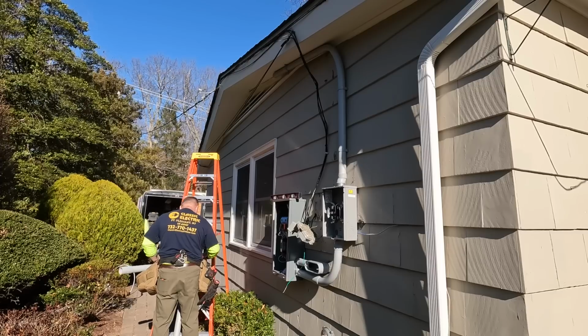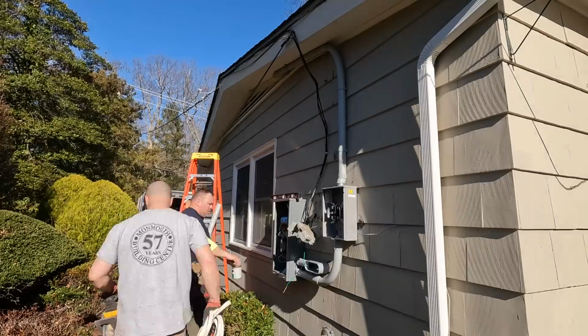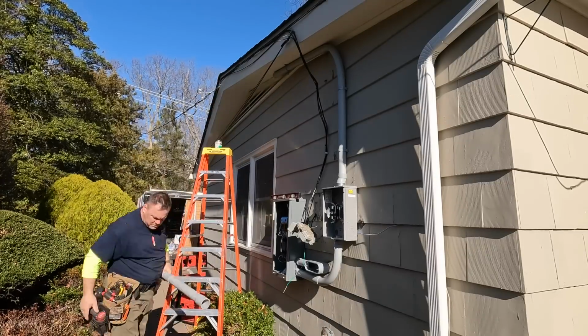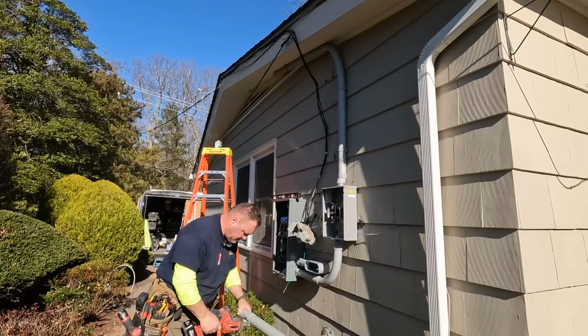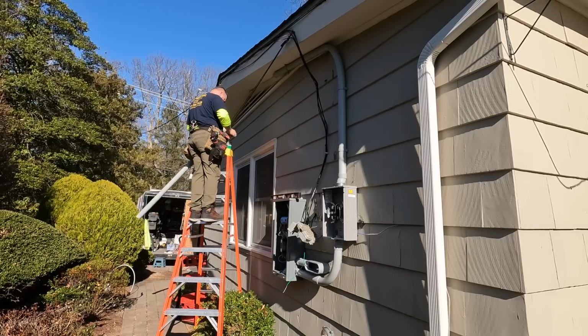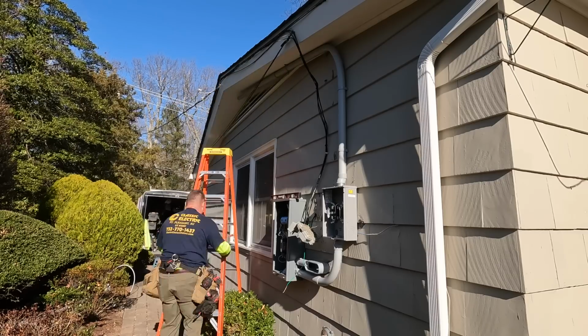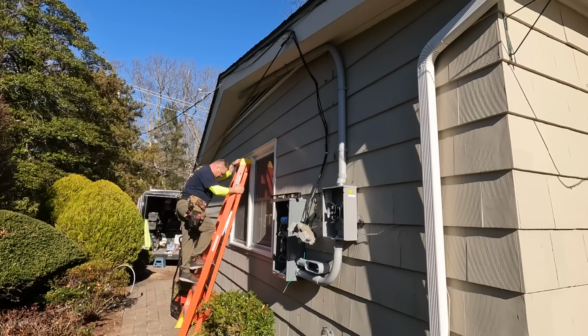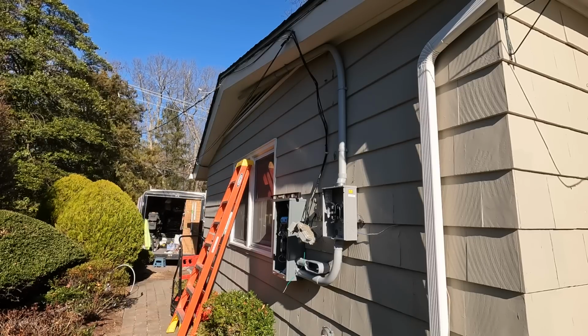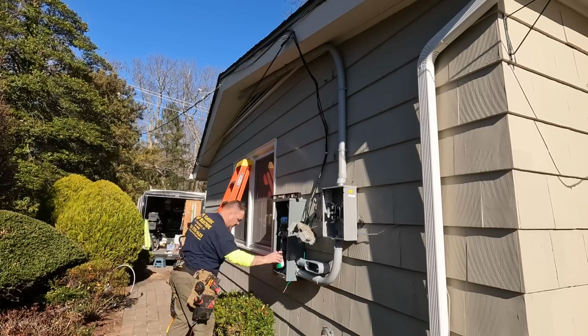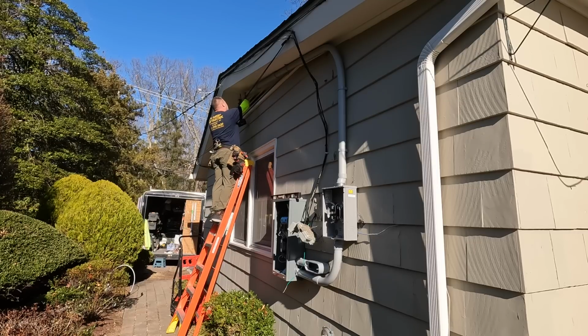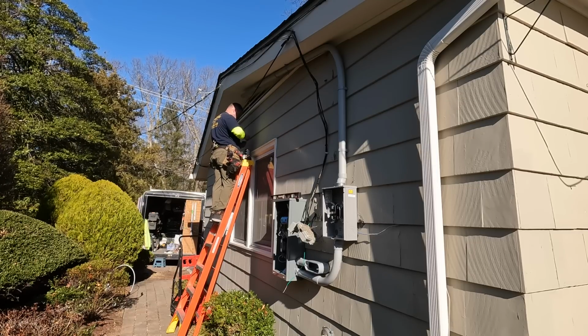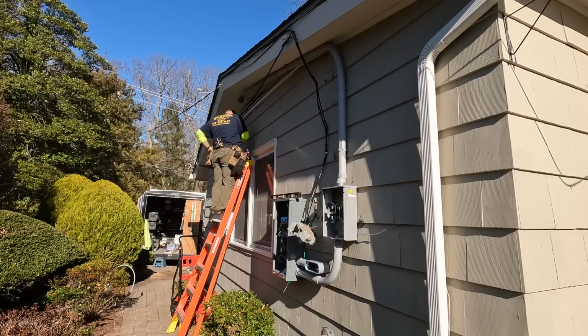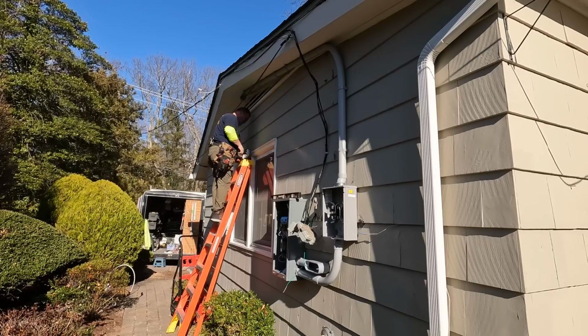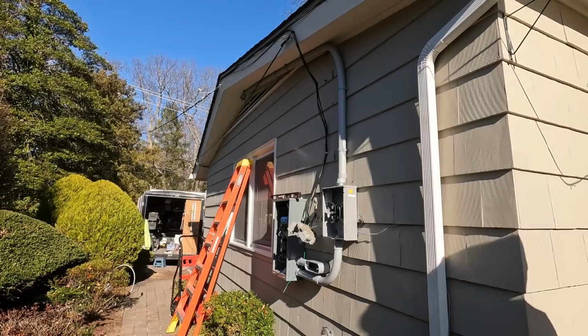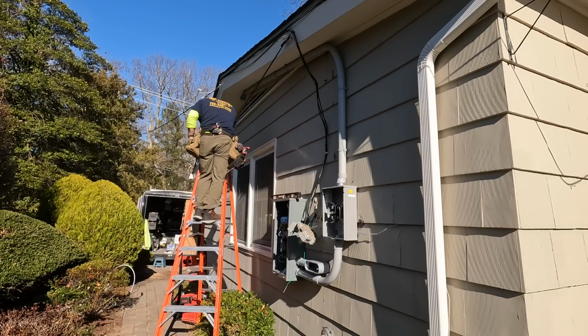This was a long day, and this is actually the first time I've ever done this on a service where I worked on the service all day, and I usually turn the power back on that same day. But this job took a little bit longer than I had anticipated with that transfer switch. You might not notice it in the video here, but it did. It took a lot longer, and I wound up not leaving this house till about 7:30 at night the first day. But being that nobody was living there, it was not an issue to leave the power off until the next morning when I came back, and then the electric service was restored by around noon the following morning. But for today, the grounding was done the first day. All this other work was done the second day. And then finally on the third day, I'm going to connect all the branch circuits, which you'll see momentarily here.